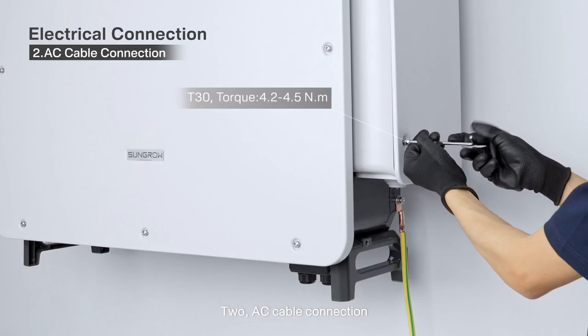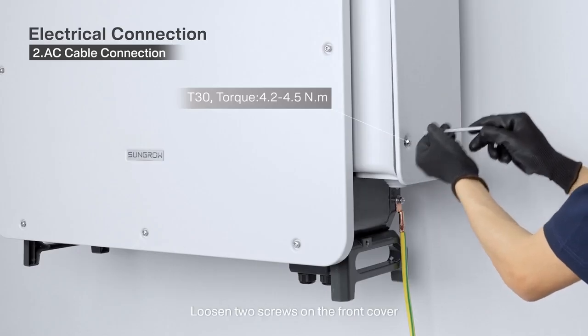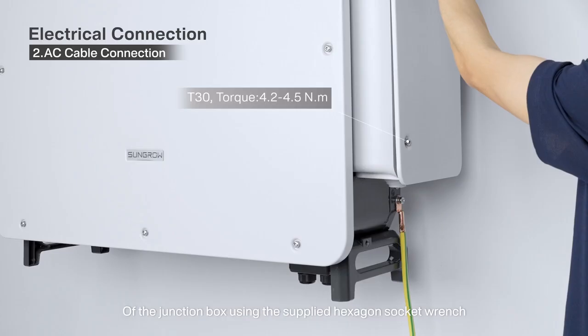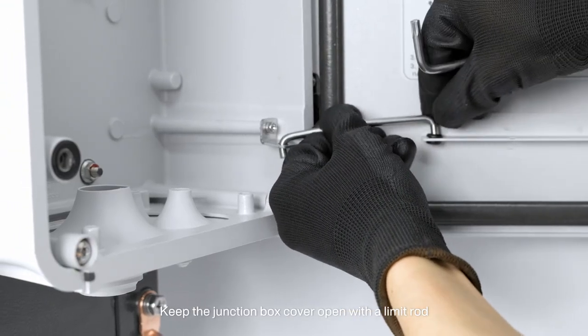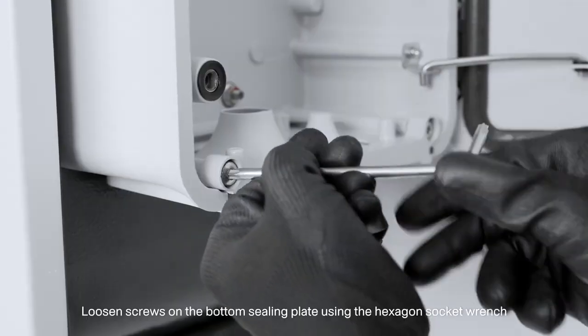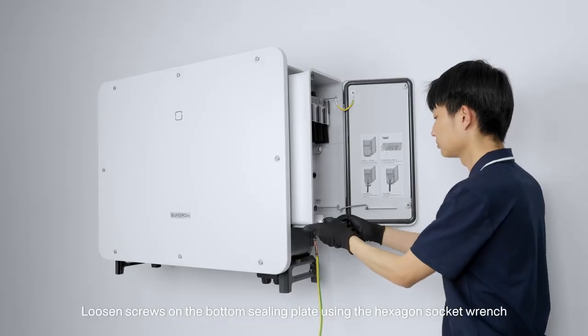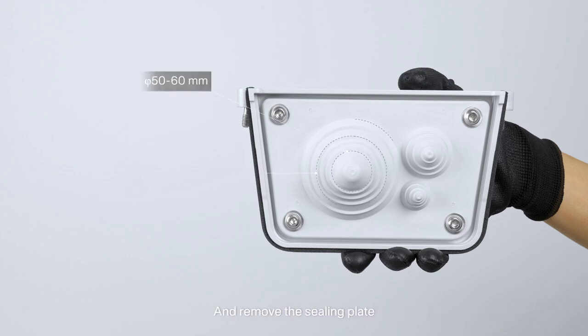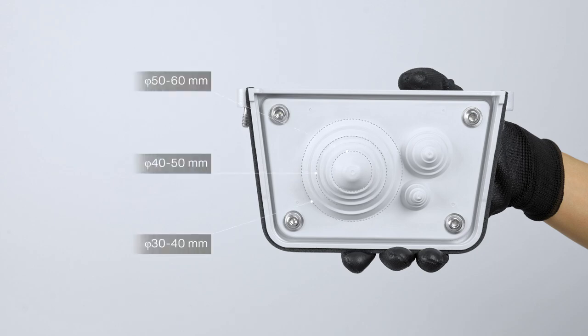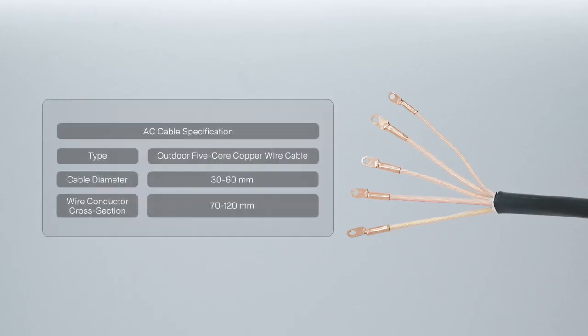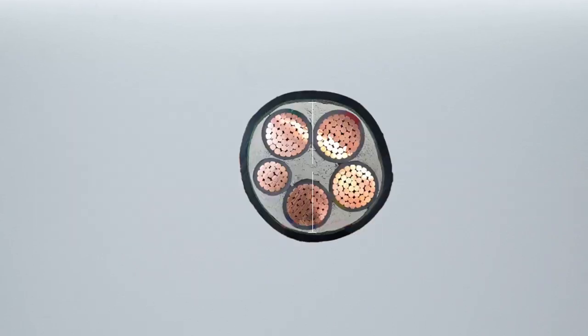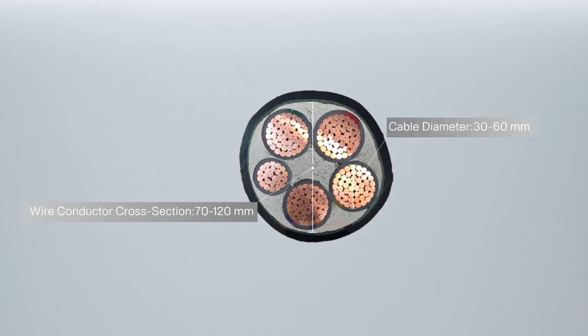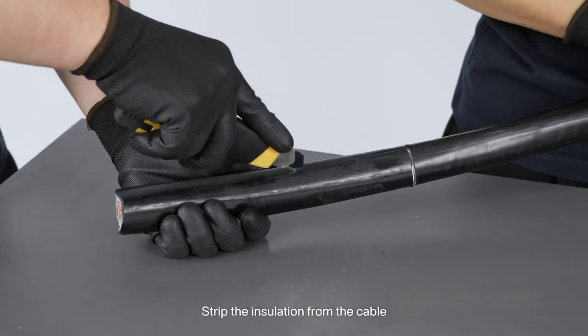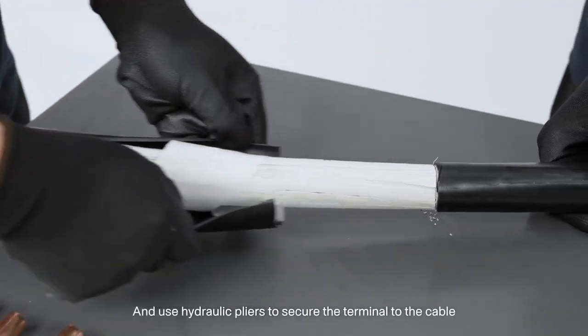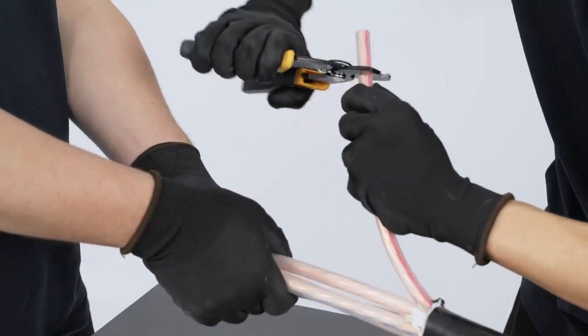2. AC cable connection. Loosen 2 screws on the front cover of the junction box using the supplied hexagon socket wrench. Keep the junction box cover open with a limit rod. Loosen screws on the bottom sealing plate using the hexagon socket wrench and remove the sealing plate. Strip the insulation from the cable and use hydraulic pliers to secure the terminal to the cable.